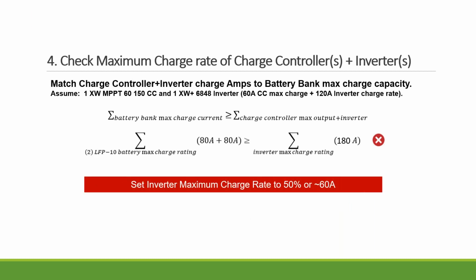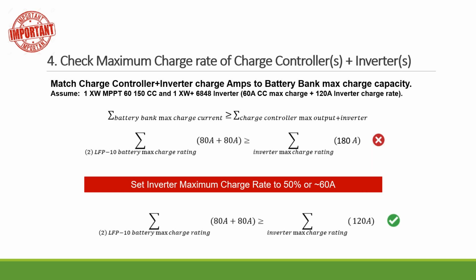Step 4 is to check the maximum charging rate of the charge controller combined with the inverter. In these systems, for example, here we use one XW MPPT 6150 and one XW 6848. In these cases, the charge controller's maximum charge amperage is 60 amps, and the inverter's maximum charging rate is 120 amps. That's according to the specs.